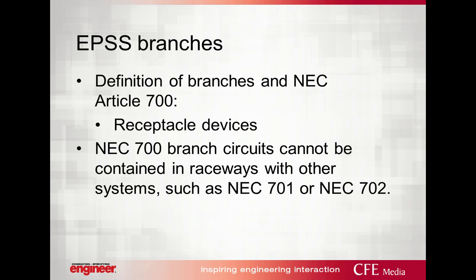The reality is this: we as engineers don't know what people are going to plug into that. They might put a space heater, for instance, which may, because of lack of selective coordination, instead of tripping the branch circuit because of a failure of that piece of equipment, take out the main breaker upstream. So there are several items there that are at fault. Number one, no selective coordination or little selective coordination. The code requires complete selective coordination on an Article 700 system, and we'll talk more about that later. But in all cases, try to avoid putting receptacles on emergency power, Article 700.